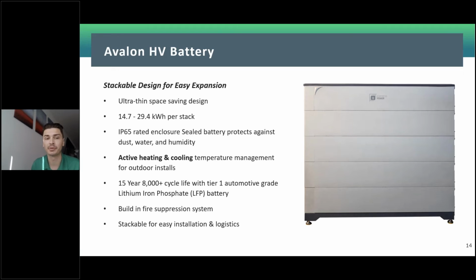It is still LFP, but we're working in a higher voltage, hence the name high voltage battery, because each one of these batteries is 48 volts, and we're wiring them up in series through this side panel. That is also where you'll have the heating element connected. The BMS sits on top, which is where you'll have a 60 amp breaker, and you'll have communication cables running from each battery, with the battery pack going to the inverter. Fire suppression is also built in, and because of its stackable nature, it's very easy for installation and logistics.